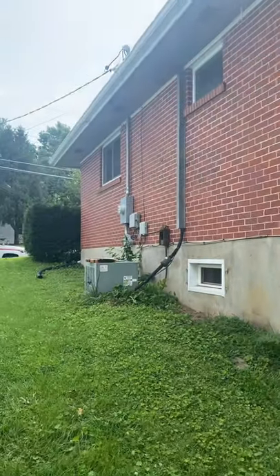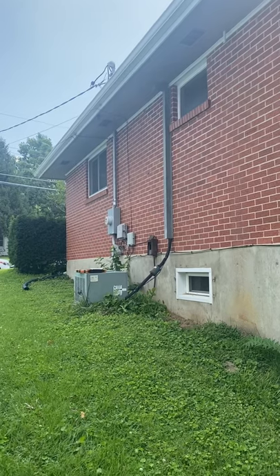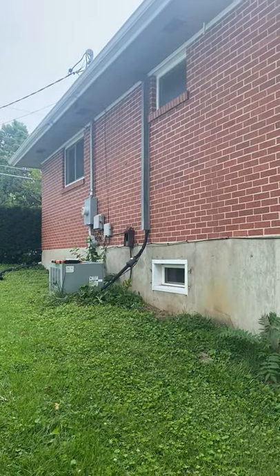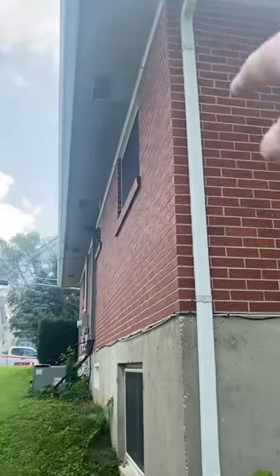Outdoor unit — after some more discussion with the homeowner after coming out of the attic, we noticed the supply line is too small, so it's going to have to get rerun. Since we're doing that, the homeowner would like to go ahead and move the condenser to this back corner right here, so the line sets would just run from the attic, just like they're doing right there.